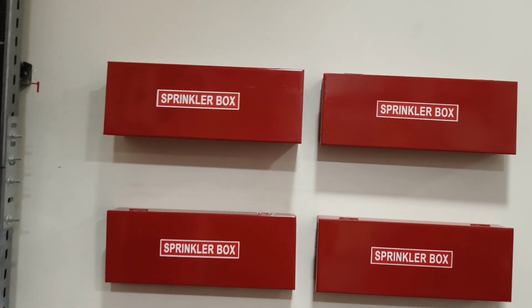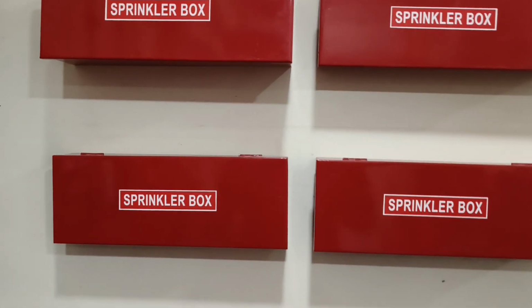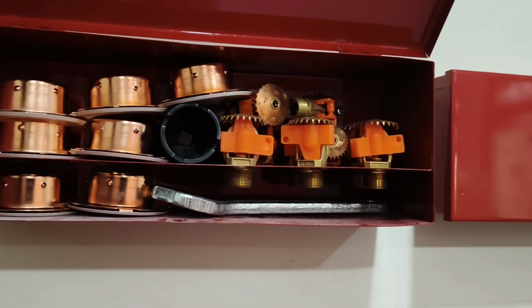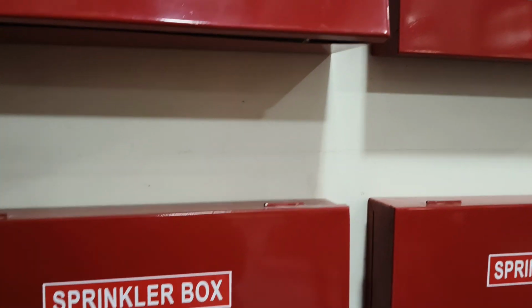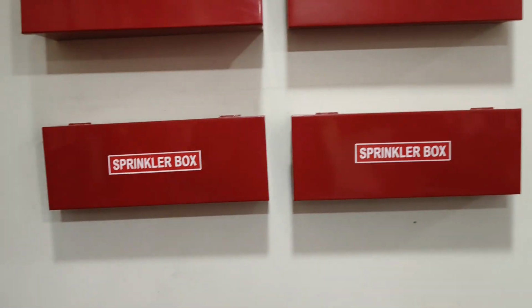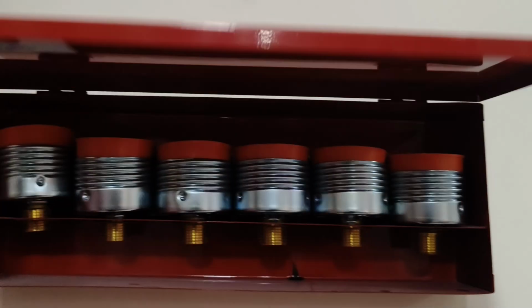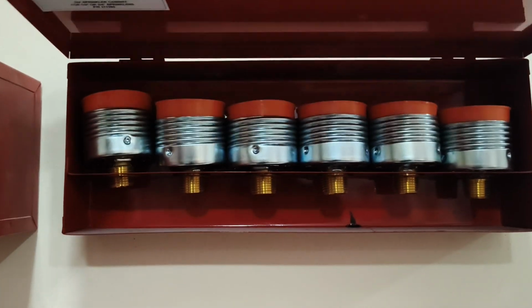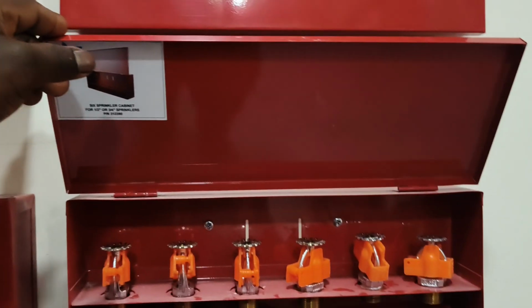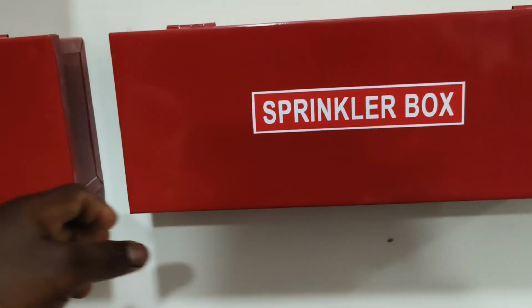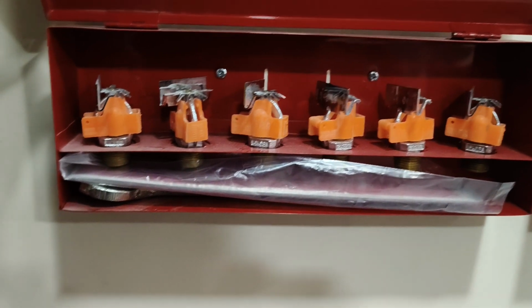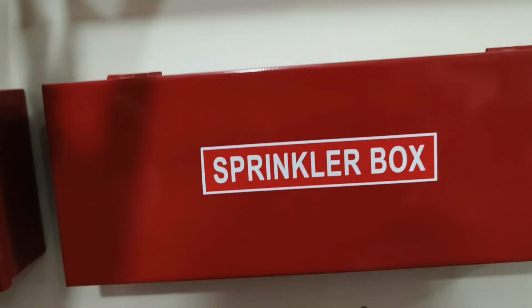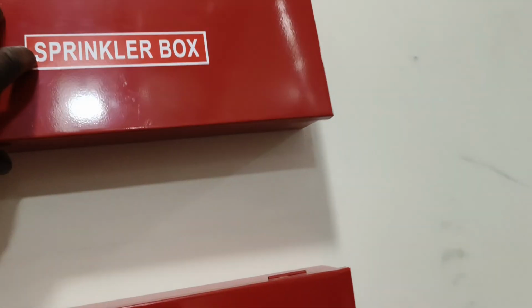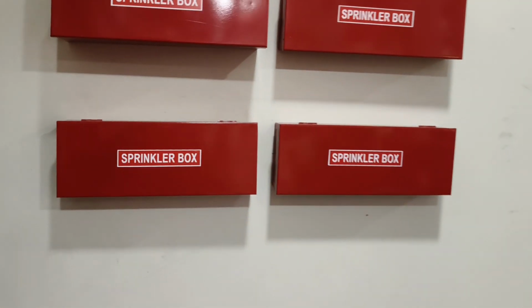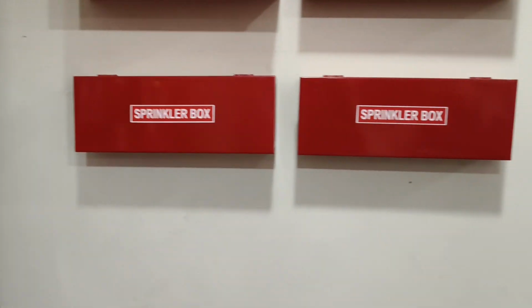So every fire pump room has to have sprinkler boxes, and the purpose of the sprinkler box is to have spare sprinklers, so in case of any emergency you could just get some from here to fix on site. You're supposed to have different kinds - the ones that have been installed, all kinds and types you're supposed to have. If you installed sidewall, pendant, upright, or concealed type, you need to keep spare inside the sprinkler box in the fire pump rooms.